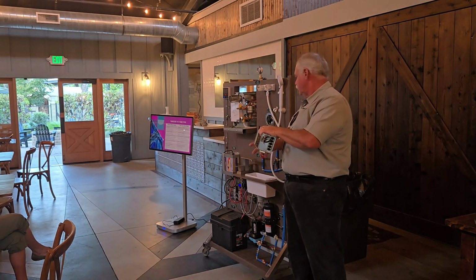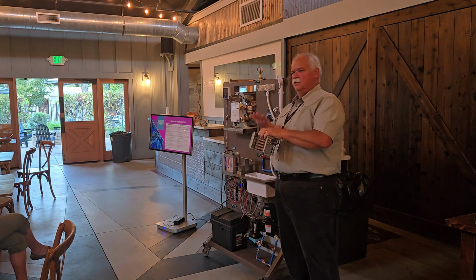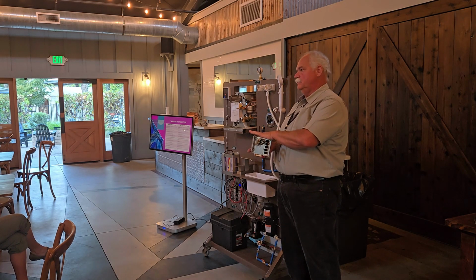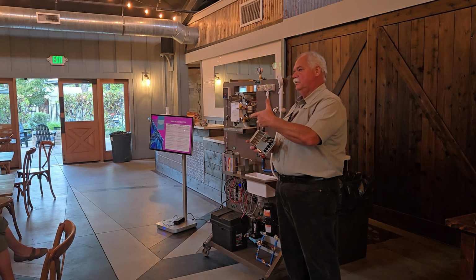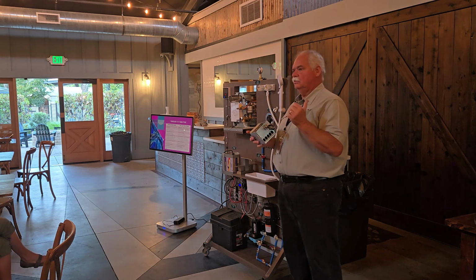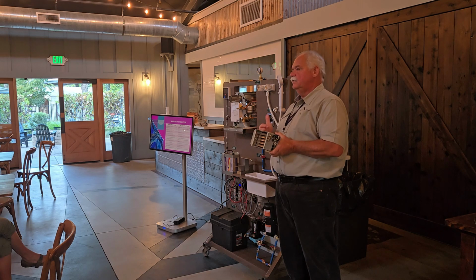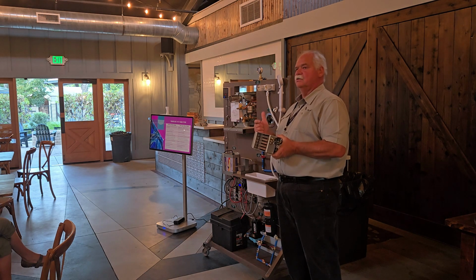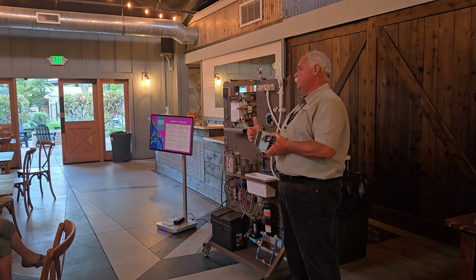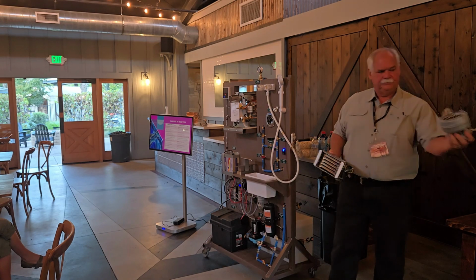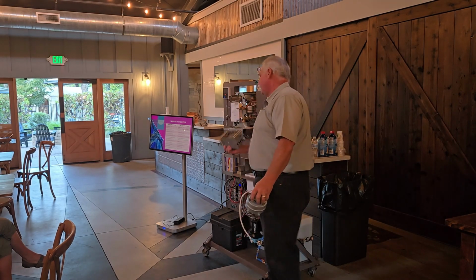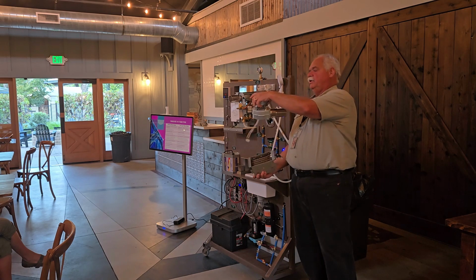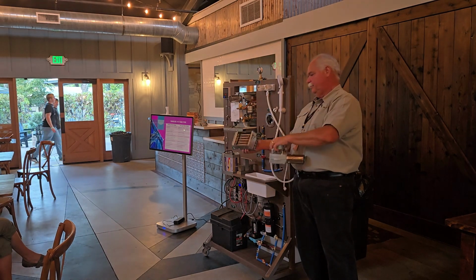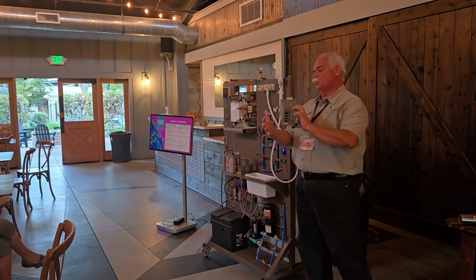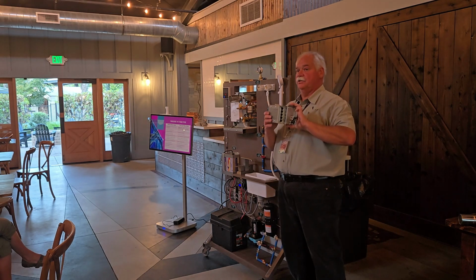So when I first turn on my hot water faucet, this thing is going to come on at 65,000 BTUs. All 5 burners are going to light. I have what's called a proportional flow valve that's going to adjust how much propane it sends to it. It's going to send the maximum amount of propane to all 5 burners. Then we take this fan, which sits on the top, and our heat exchanger is going to sit between here, and we're going to blow air out, which means we're going to pull the air in from the bottom of this heat exchanger.